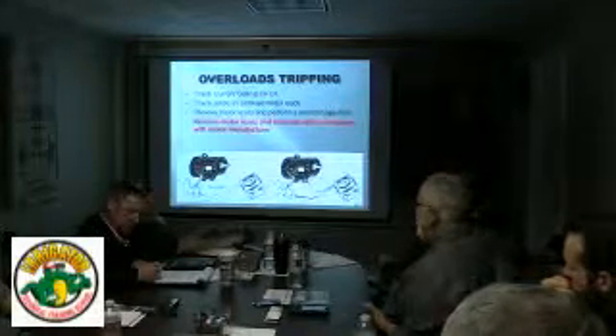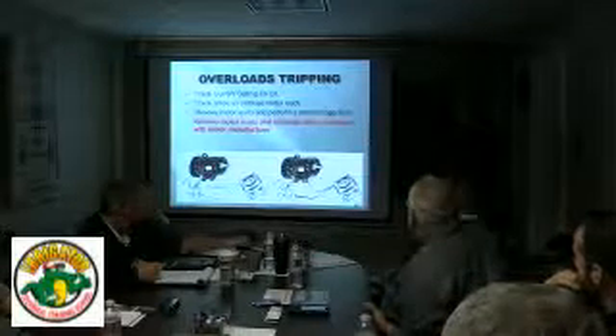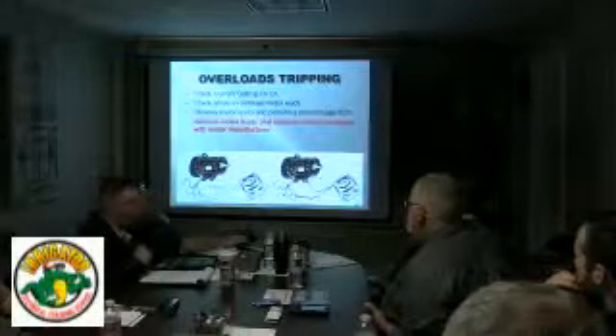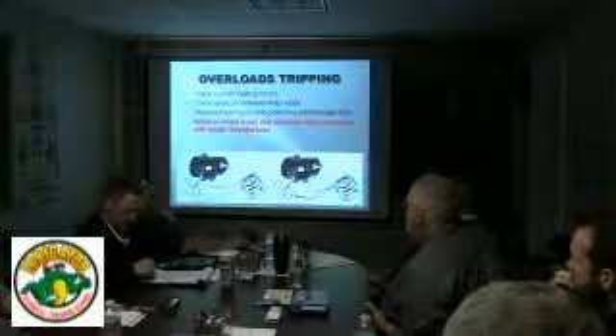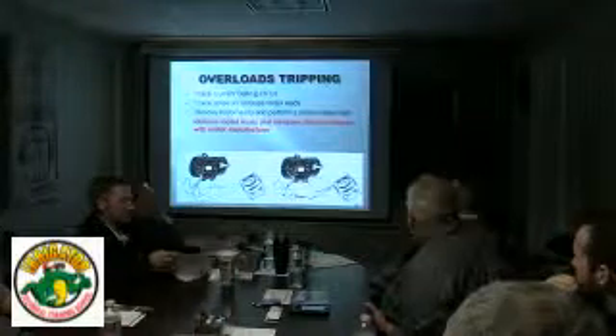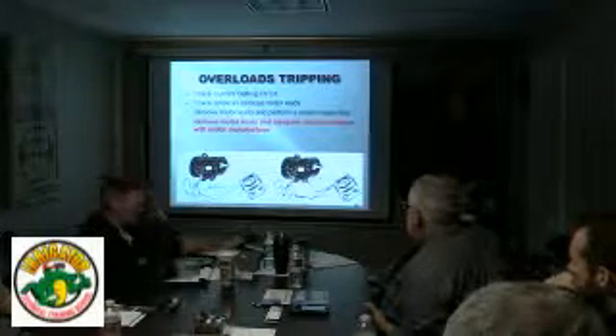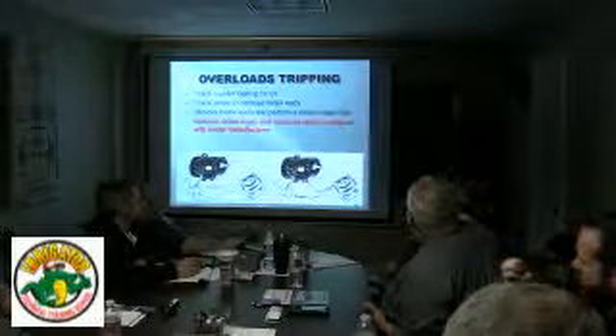As long as it's wet, you don't want to try to meg it. You don't want it to dry out or blow it out. That's true, it'll show bad if it's got much moisture in it. See that a lot in my area. Your leads can get saturated too, submersible leads cause an issue. Or a little nick in the cable when you're putting it down or something.